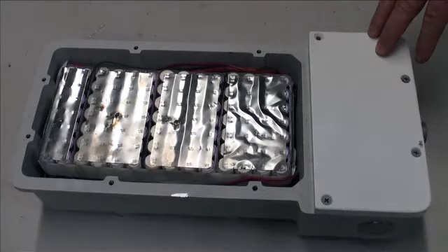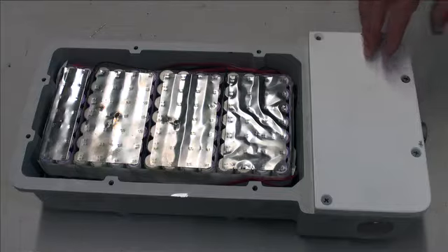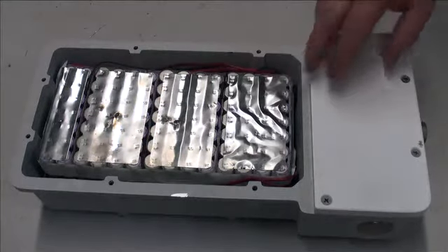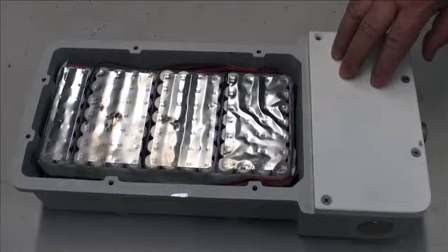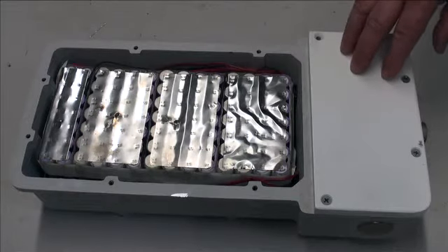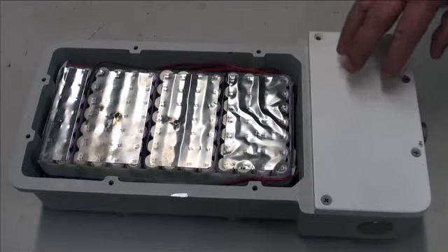This is a lithium-ion battery brick which is wired together both serially and in parallel to continuously charge and discharge. This energy management system allows us to operate with the batteries fully charged at all times, not using up the 15,000 charge-discharge life cycles. During operations, we use the solar panels for the LED lighting in the plant.